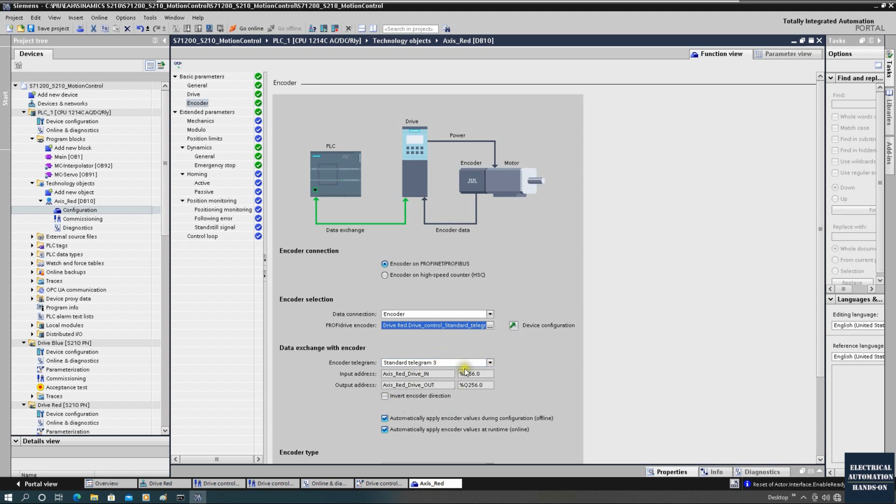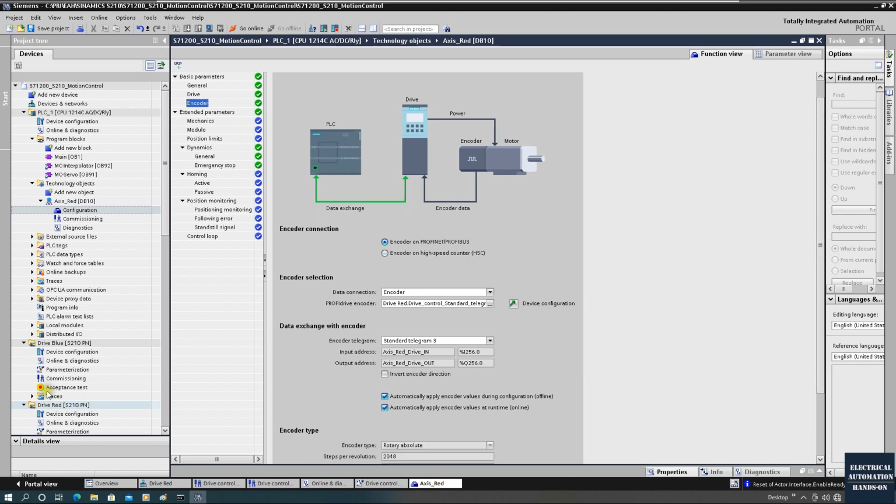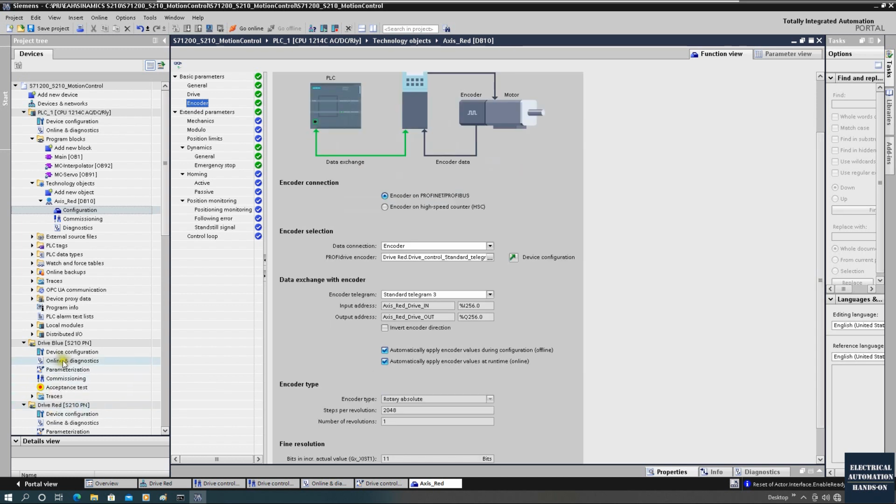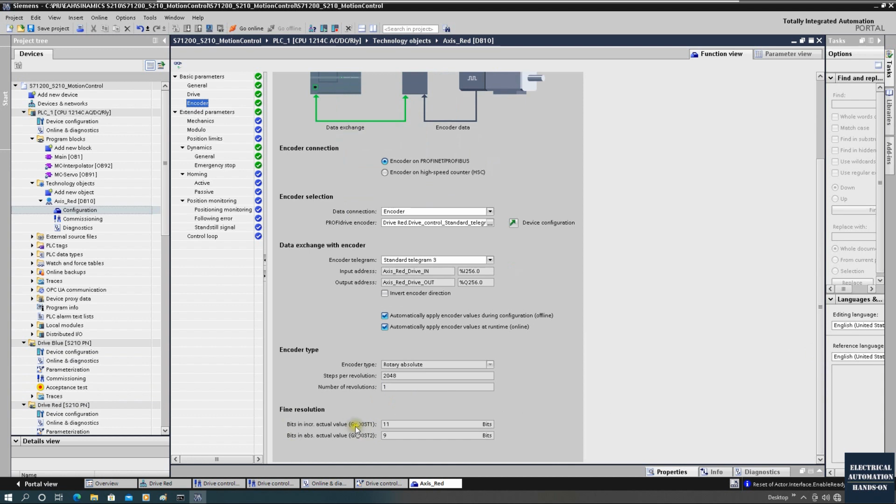Okay, automatically updated. Again, if the encoder value shows backward compared with your tool direction, you can also invert. And more importantly here, since we configure this drive via Startdrive, when we offline pick up the encoder, all those encoder parameters, especially the protocol behind, like this XIST1, XIST2, are all automatically selected.